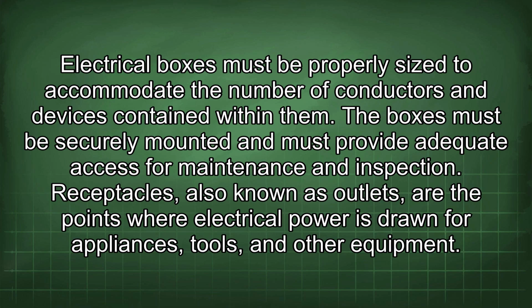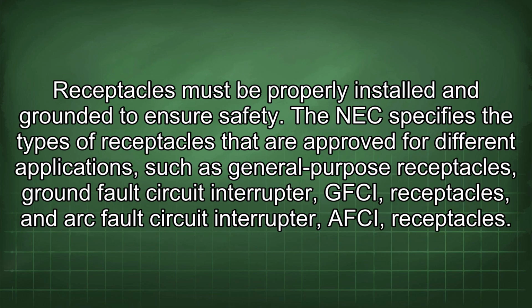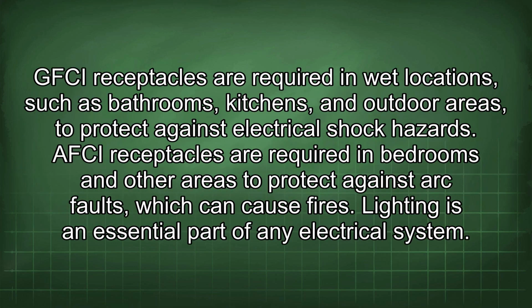Receptacles, also known as outlets, are the points where electrical power is drawn for appliances, tools, and other equipment. Receptacles must be properly installed and grounded to ensure safety. The NEC specifies the types of receptacles that are approved for different applications, such as general-purpose receptacles, ground fault circuit interrupter, GFCI receptacles, and arc fault circuit interrupter, AFCI receptacles. GFCI receptacles are required in wet locations such as bathrooms, kitchens, and outdoor areas to protect against electrical shock hazards. AFCI receptacles are required in bedrooms and other areas to protect against arc faults, which can cause fires.